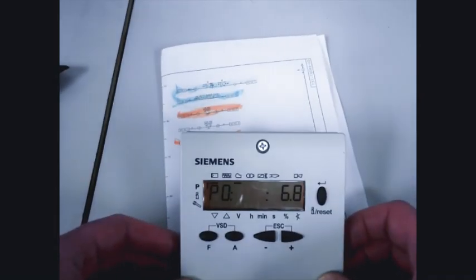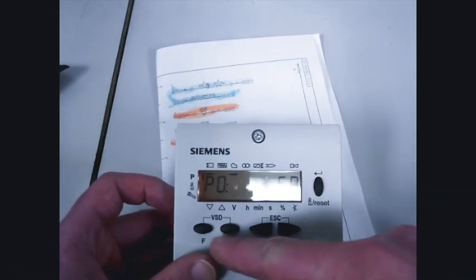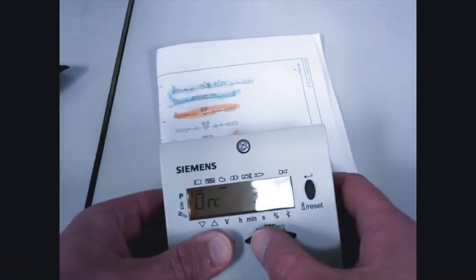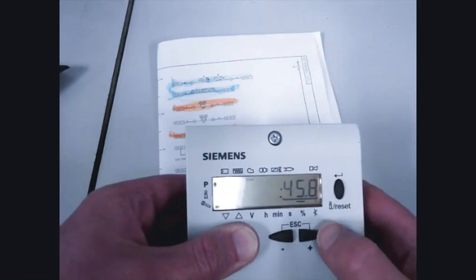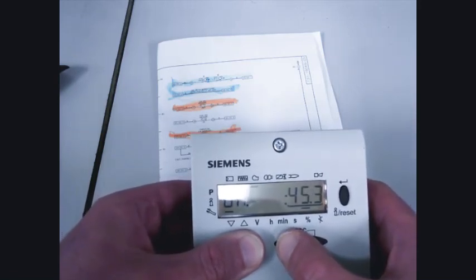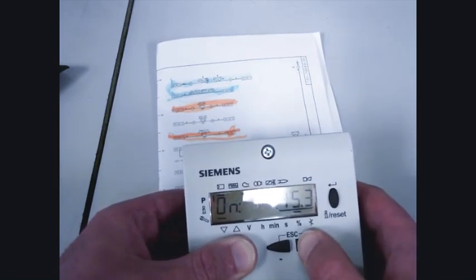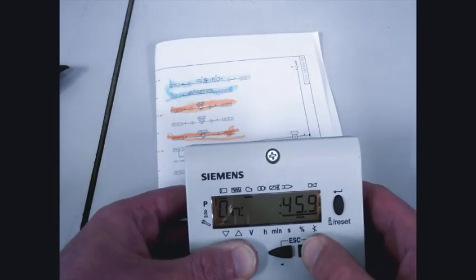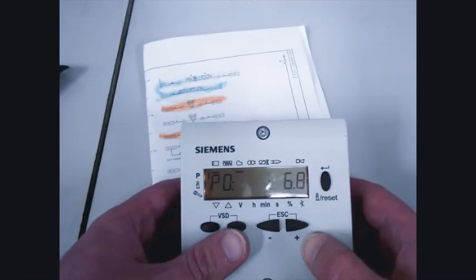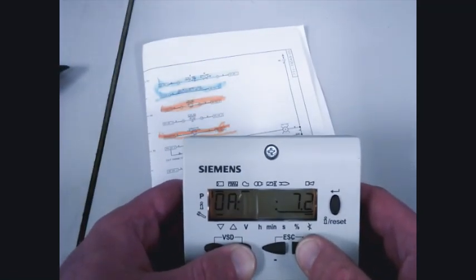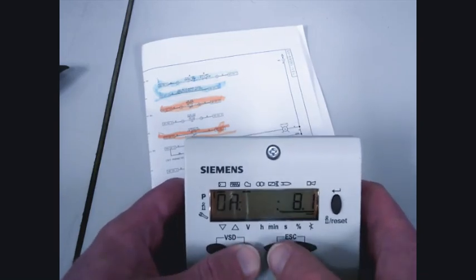We are now at P0, our light off point. From here we can change the fan speed by pressing F and A to get to the VSD. Press plus to increase the speed and release, or minus to lower it — which it adjusts in real time. Hold down A to adjust the gas butterfly by pressing plus or minus while holding A.